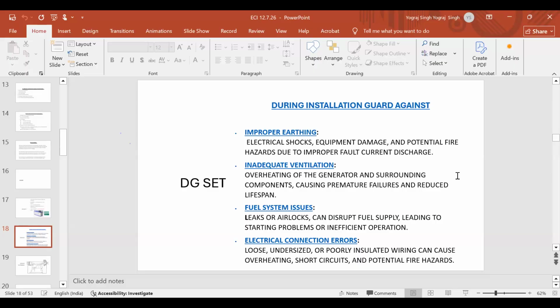Now when you are installing a DG set, if the earthing is not proper, it can lead to electrical shocks, equipment damage, and fire hazards due to improper fault current discharge. Fault current discharge into the ground is very, very important. Ventilation needs no further explanation. The fuel system is important. The fuel system should not leak, otherwise it can lead to fire hazards and other problems.